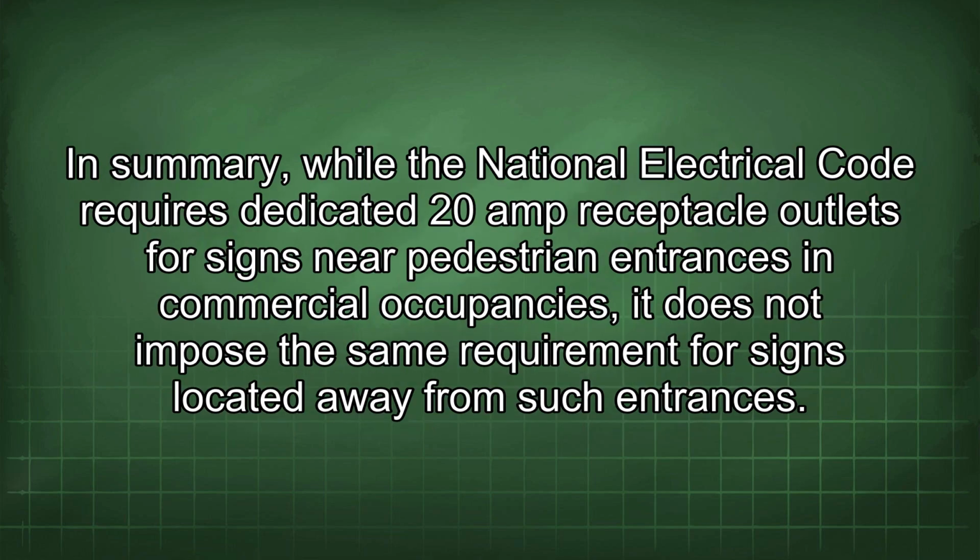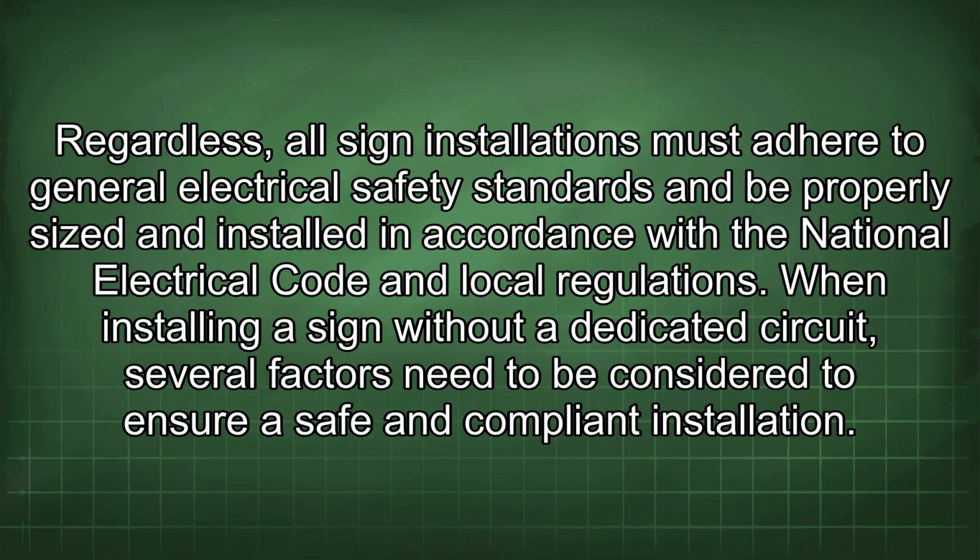In summary, while the National Electrical Code requires dedicated 20 amp receptacle outlets for signs near pedestrian entrances in commercial occupancies, it does not impose the same requirement for signs located away from such entrances. Regardless, all sign installations must adhere to general electrical safety standards and be properly sized and installed in accordance with the National Electrical Code and local regulations.